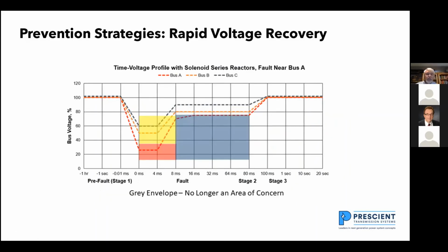Anyhow, this is the same system with solenoid series reactors. Now these are put in series with transmission circuit breakers in substations. And this is showing that in 8 milliseconds, voltage recovers from 0 at bus A to 70%, to 80% at bus B, and to 90% at bus C. And this gray area here is where the fault is still on the system. The circuit breakers haven't isolated the fault, but the system impedance was changed by the solenoid series reactors, and that changed the voltage transient to an 8 millisecond transient.